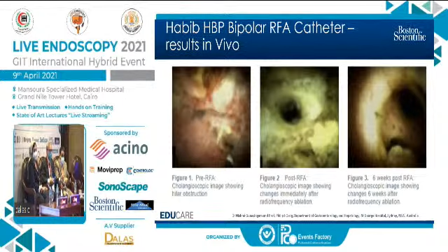How can you control the depth of the ablation while you cannot see during the procedure? That is exactly a good question. We know by the geometry of these 8 mm electrodes, with 8 mm space in between, plus 8 mm, that it adds up to 24 millimeters. We know exactly that this ablation algorithm of 90 seconds at 10 watts creates a 2.5 centimeter ablation zone by 1 centimeter. So it's consistent. On most of the electrosurgical generators from the Erbe company, you have this smart meter showing you that energy is applied, and you are absolutely under control of that. Once you put a pedal for 90 seconds, you can absolutely trust, from more than 13,500 procedures done, that this is the outcome.